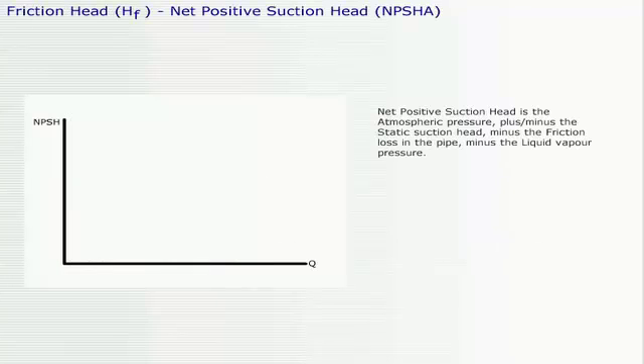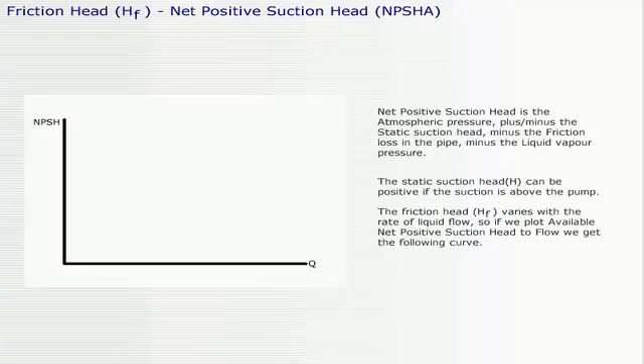Net positive suction head is the atmospheric pressure, plus or minus the static suction head, minus the friction loss in the pipe, minus the liquid vapor pressure. The static suction head can be positive if the suction is above the pump. The friction head varies with the rate of liquid flow. So, if we plot available net positive suction head to flow, we get the following curve.